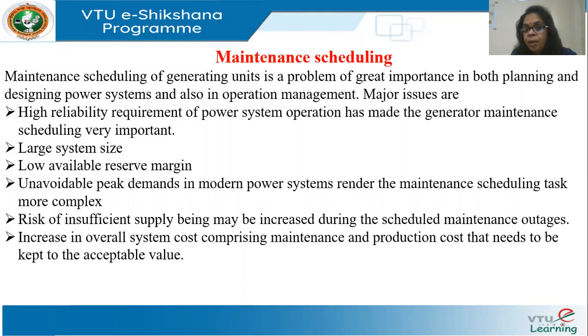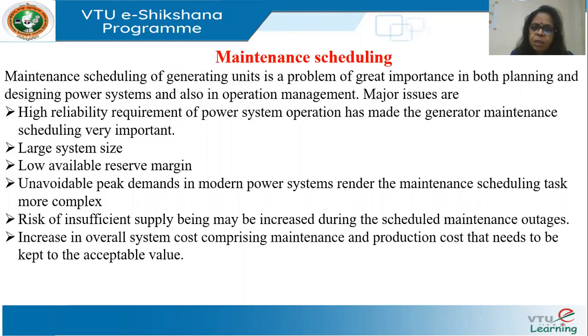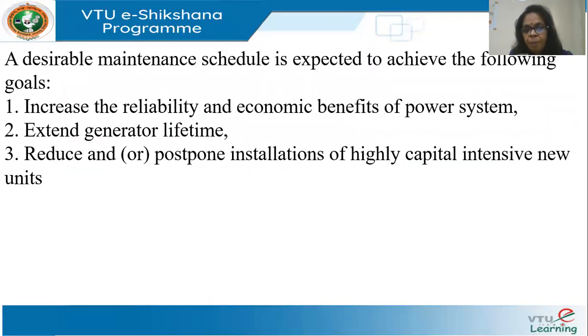In modern grids, because of the nature of the loads, sudden peak demands come on the system. This makes scheduling for maintenance a difficult and complex task, because during maintenance you may be able to meet the base load, but you may not be able to meet a sudden peak load which occurs. Insufficient supply may be increased during scheduled maintenance outages, and of course cost — everything involves cost. These are some issues which have to be borne in mind when the system is maintained.